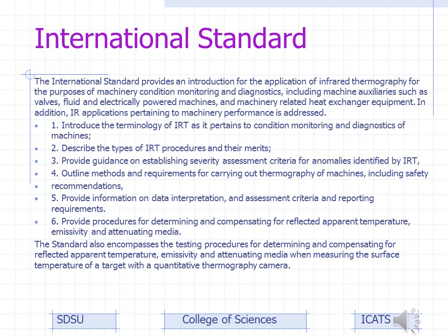It provides guidance to establishing severity and assessment criteria for anomalies identified by infrared thermography, and there are different criteria set up there because it's not internationally standardized as of yet. Although I do find that those international standards, the ISO standards that they just suggest in there, are very adequate for calling out most problems. I've seen scales that were higher than that, and potentially problems could have arisen from issues with that different standard.